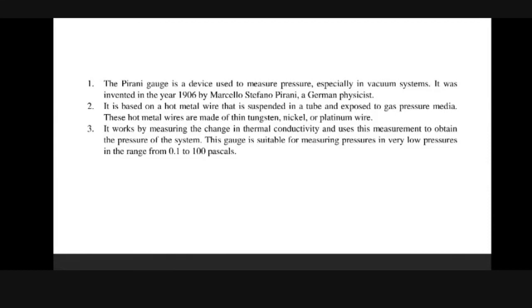Gauge is a device used to measure pressure, especially in vacuum systems. It was invented in the year 1906 by Marcello Stefano Pirani, a German physicist. It is based on a hot metal wire that is suspended in a tube and exposed to the gas whose pressure is being measured. These hot metal wires are made of tungsten, nickel or platinum.